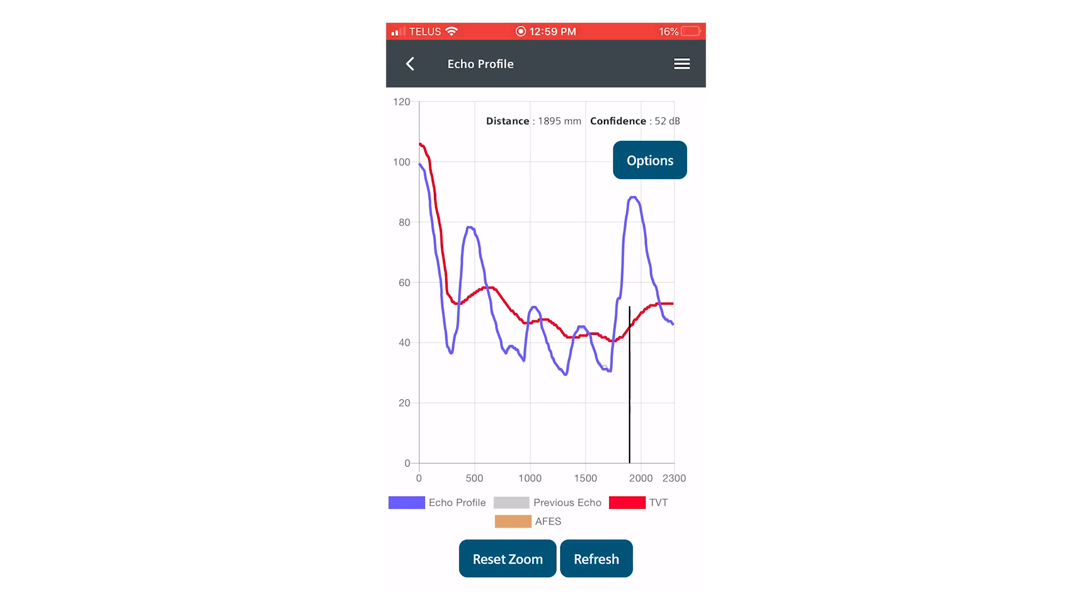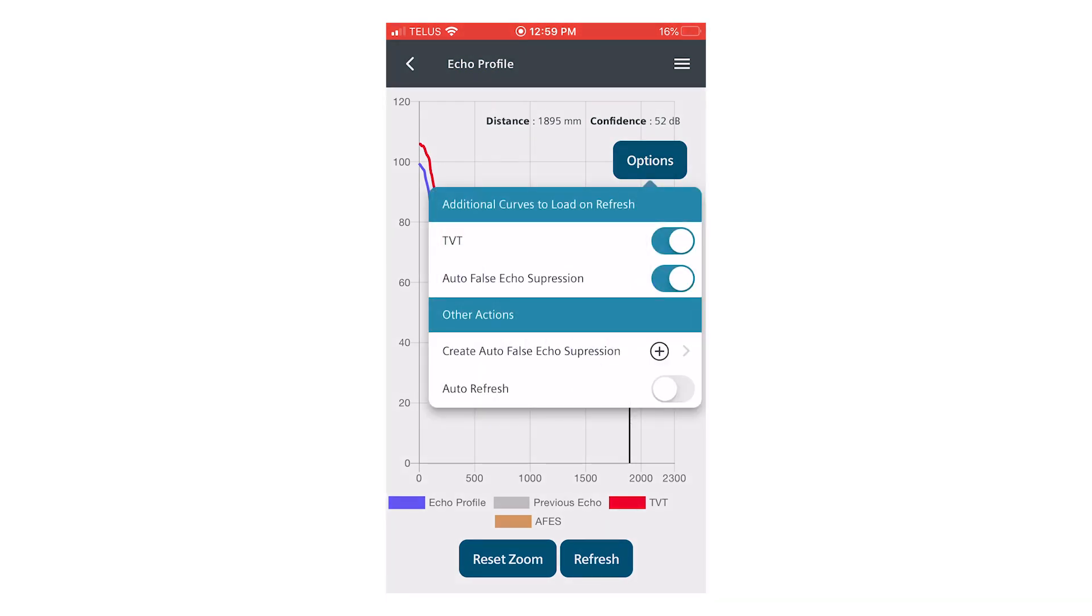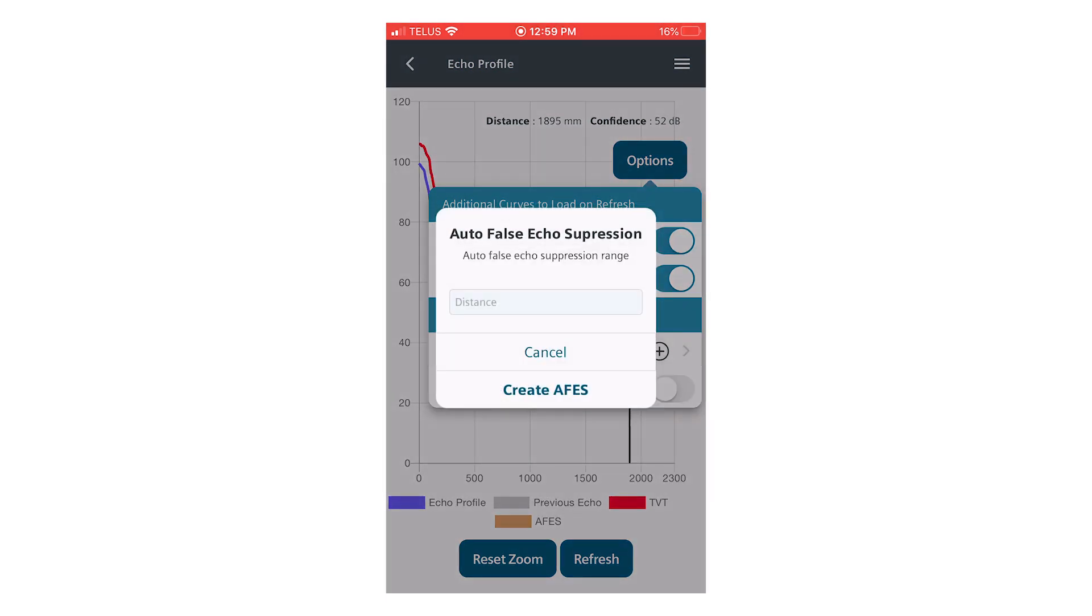To use the auto false echo suppression feature we clicked options, allow the false echo suppression curve to be displayed. That's the second button. We want to create a new one.